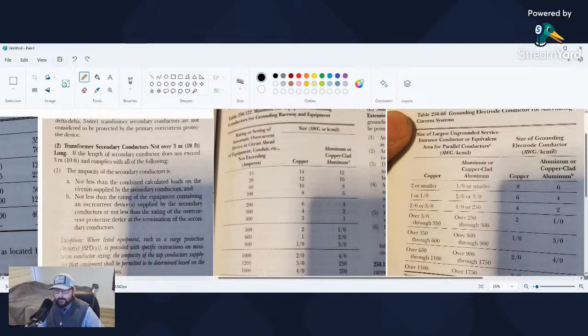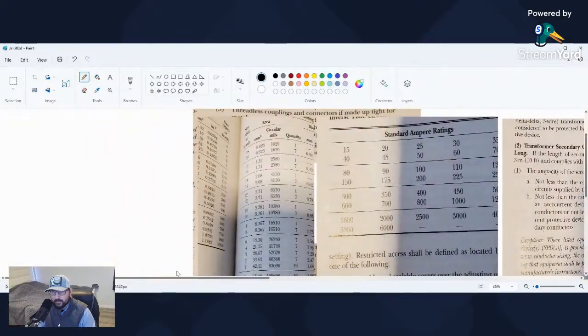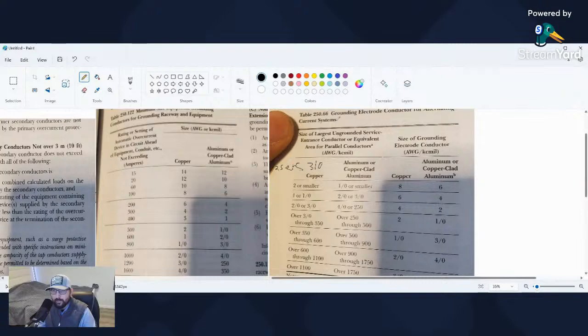Yeah, and then just for fun, I'll show you guys how to size your service ground for your transformer or your service or whatever you got. So if we've got 2 sets of 3/0, we know it's good for 200 amps each. That's going to give us 400 amps. Now, what we can't do, we can't go over here to 250.66. Well, we especially can't do it because I don't have it. Oh, we are on 250.66. My bad. We can't take a 3/0 here because we're 2 3/0s and we can't just guess.